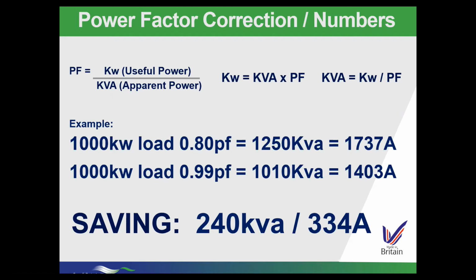Now the implication is, first of all, power that is supplied to you. You normally pay what you call an availability or a capacity charge, for the larger supplies, and it's roughly about £1 per kVA, and in some cases double that. So you can normally get a saving of around £240 a month, or I'd say even double that. But equally, if there's much less current flowing through your electrical system, then there's much less of what you call losses. Every time a current flows through a cable, you get a heating effect. That heating effect is like plugging in an electric fire: you consume energy. Those are the losses. So we're reducing the losses, basically.